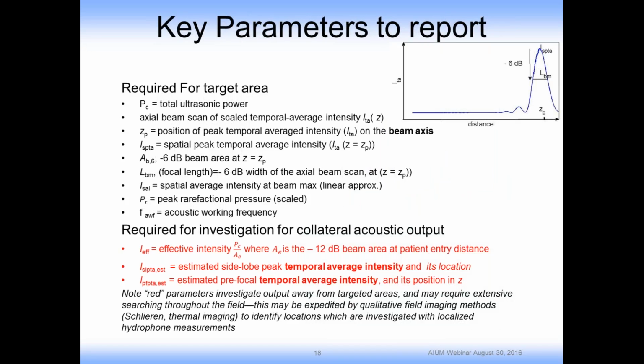I want to briefly discuss the other parameters that the standards ask you to report. First of all, there is the total ultrasonic power. An axial beam scan, basically to show how the temporal average intensity changes, is required also. Once you have that, you can also identify the position of the maximum, which is around there, and then the value at the maximum, which is the ISPTA.